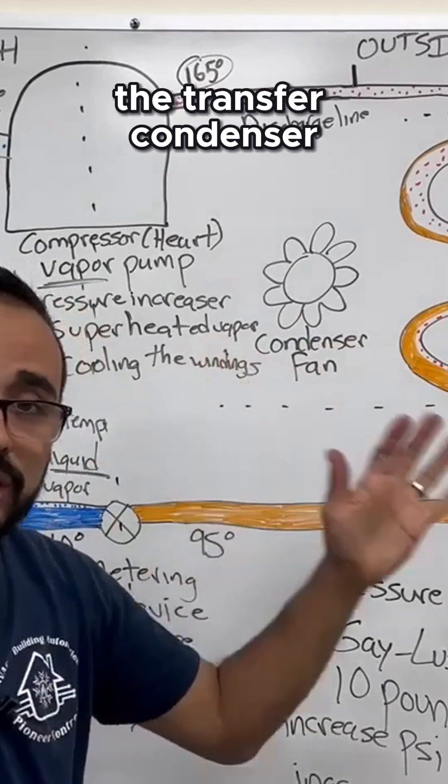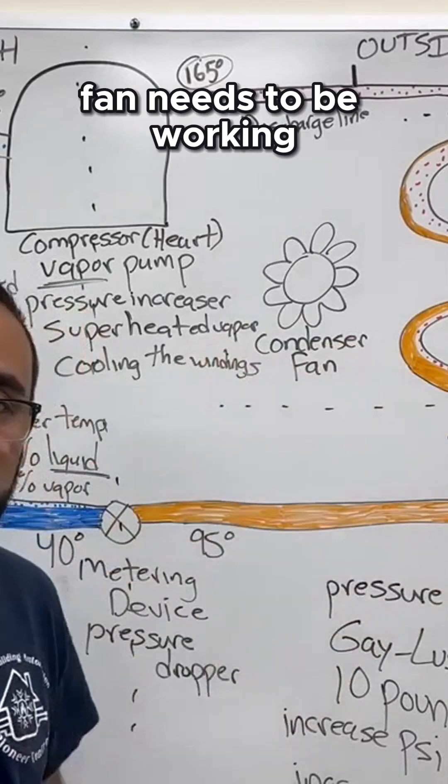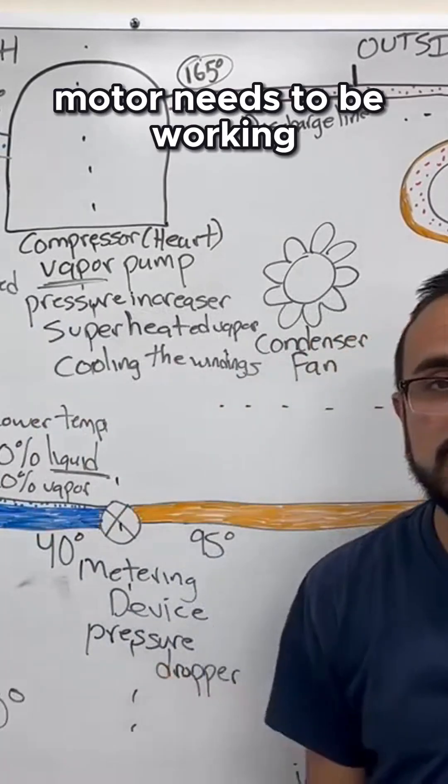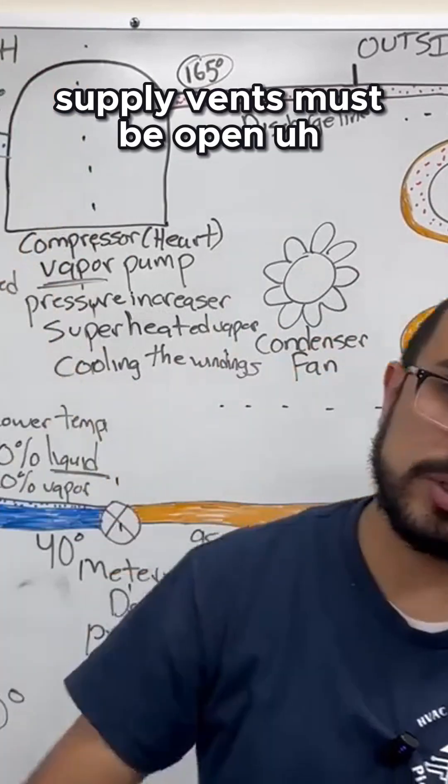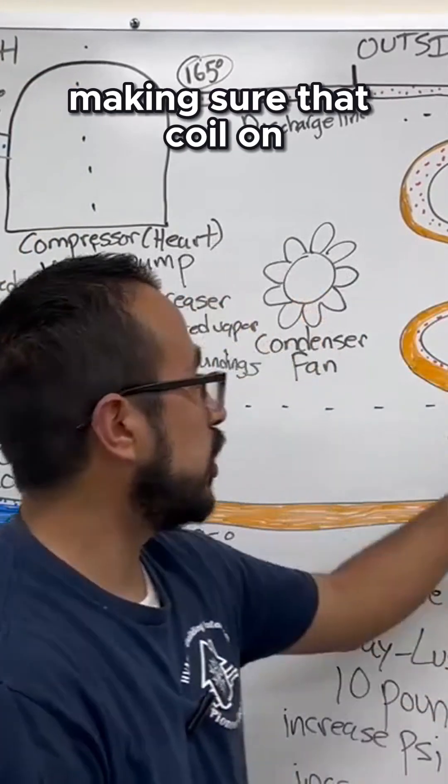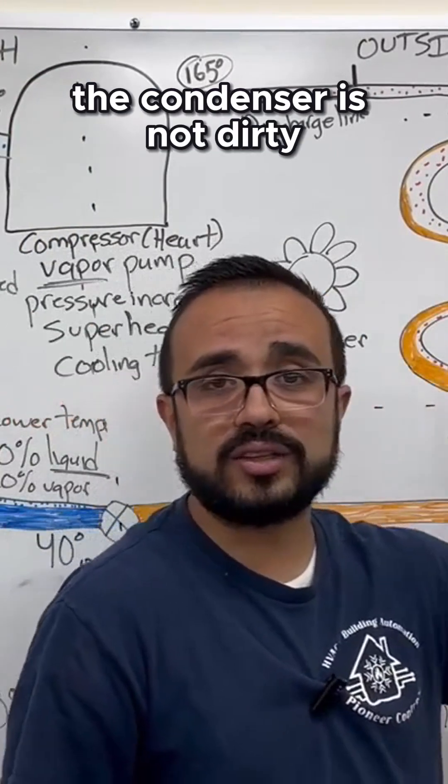And yes, you need heat transfer. Condenser fan needs to be working. The blower motor needs to be working. Cleaning the filters. Supply vents must be open. Making sure the coil and the condenser is not dirty.